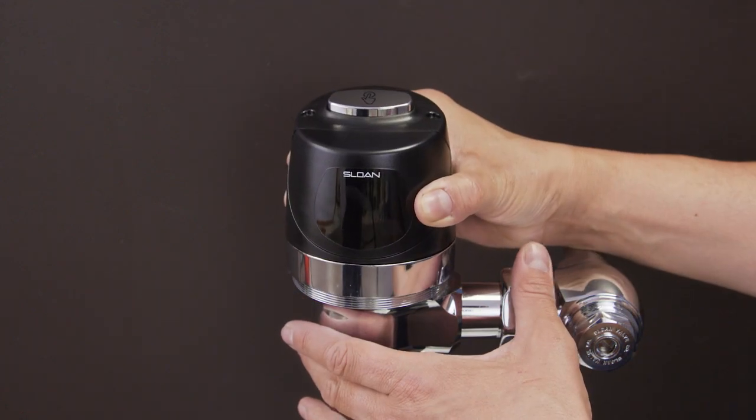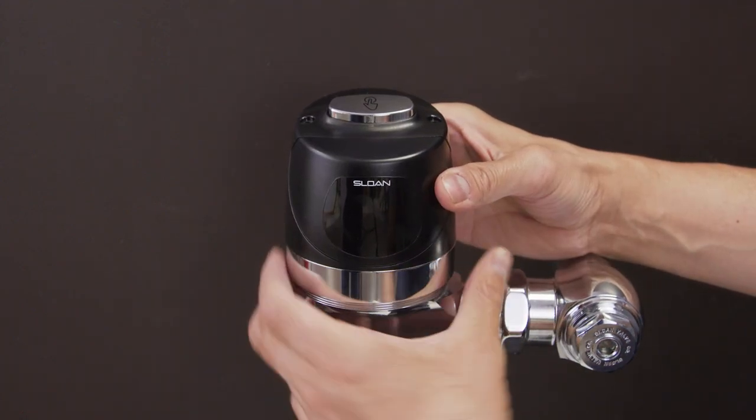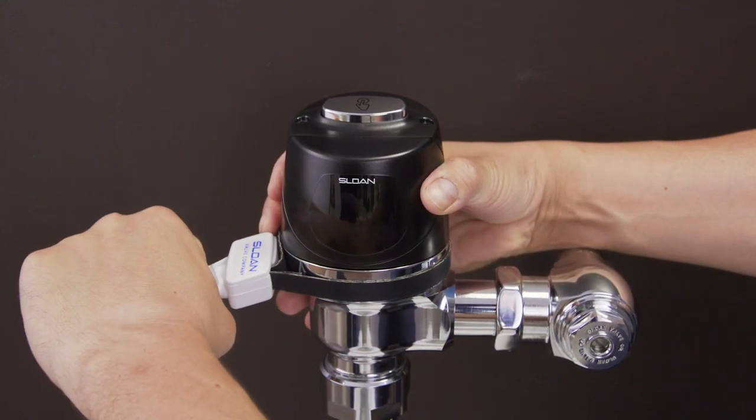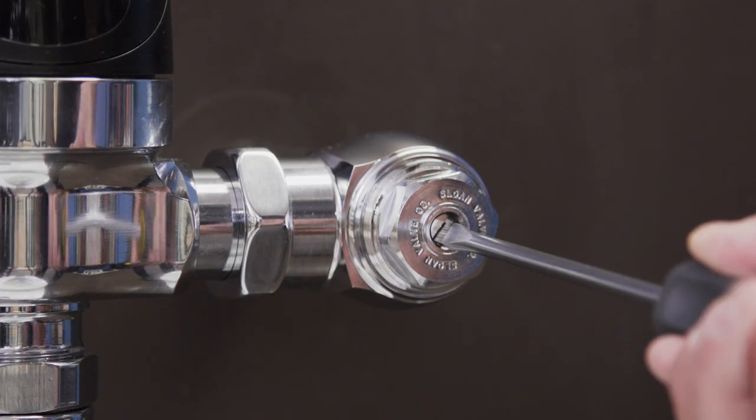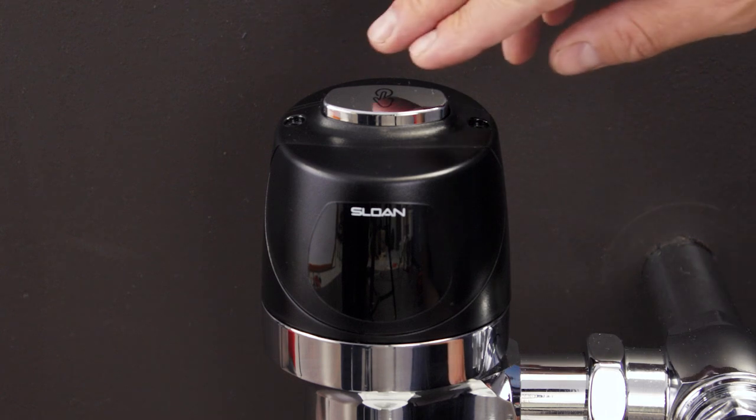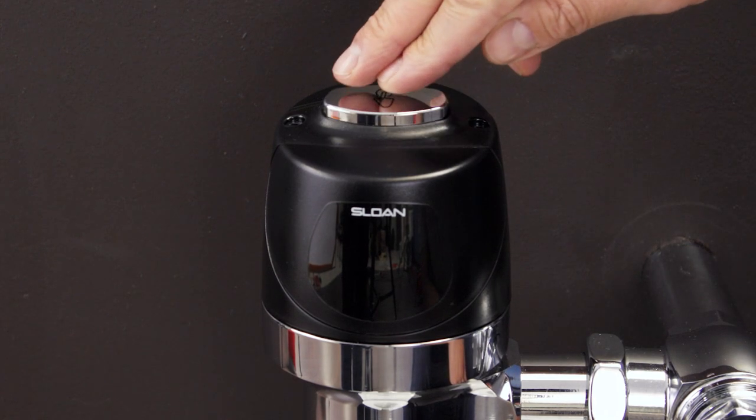Now align the head and hand tighten the locking ring. Next, use the strap wrench to secure the head. Turn on the water by opening the control stop. Now test the flushometer and adjust the control stop until you get a normal flush with quiet operation. Then finally, replace the cap.